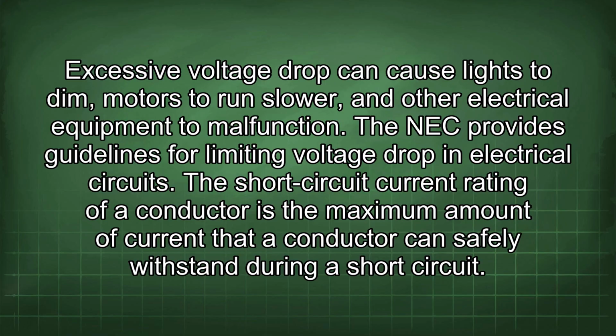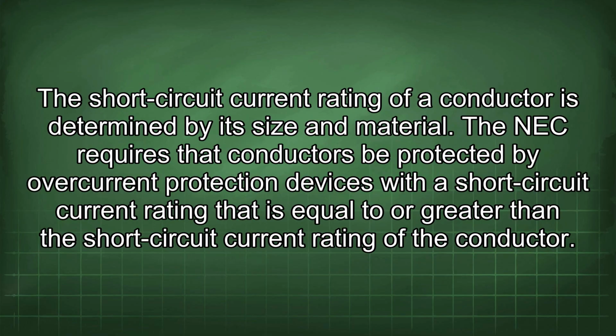The short circuit current rating of a conductor is the maximum amount of current that a conductor can safely withstand during a short circuit. The short circuit current rating of a conductor is determined by its size and material. The NEC requires that conductors be protected by overcurrent protection devices with a short circuit current rating that is equal to or greater than the short circuit current rating of the conductor.